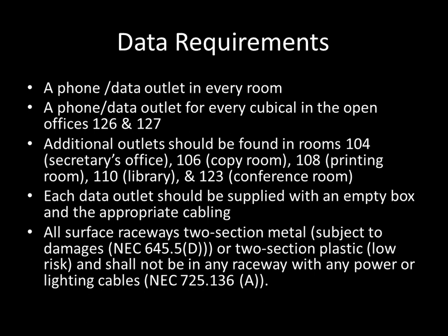Each data outlet needed to be supplied with the proper cables, which was Cat 5s, and they were needed to have an empty box for the cabling. And all surface raceways for the areas need to either be a two-section metal outline for places with such high traffic or subject to damage. Let's say if they went to kind of a walkway, you'd probably want that. But it could be plastic. And they had two different options, so it kind of got tossed a little bit. So places that you didn't need the metal, you'd probably go with plastic instead. They could not be run with the lighting or power because the NEC forbids it. So please don't do that, people.